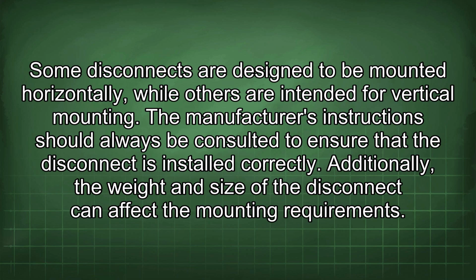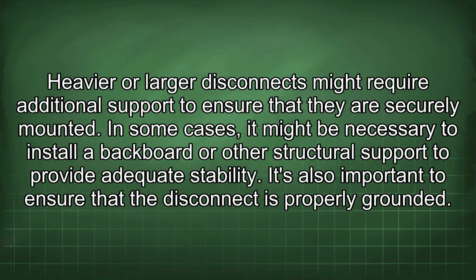Additionally, the weight and size of the disconnect can affect the mounting requirements. Heavier or larger disconnects might require additional support to ensure that they are securely mounted. In some cases, it might be necessary to install a backboard or other structural support to provide adequate stability.